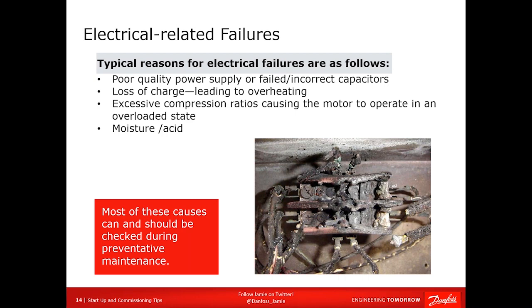This absolutely has to be corrected, because I don't care what you do, if you have poor power factor, that's another one, or poor voltage, you are going to lose the compressor. What's the point of putting a new compressor in and reusing the old capacitors that you haven't checked or confirmed are working, right, just to have it happen again?